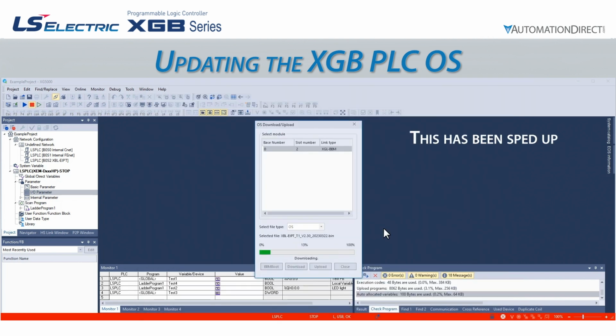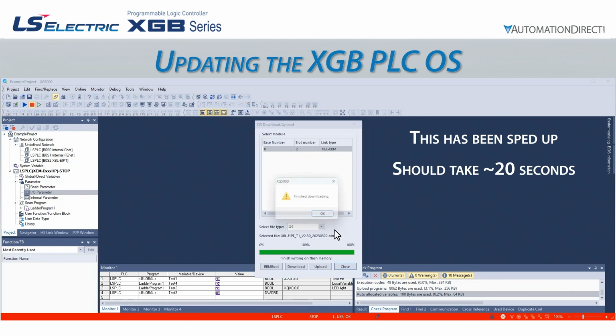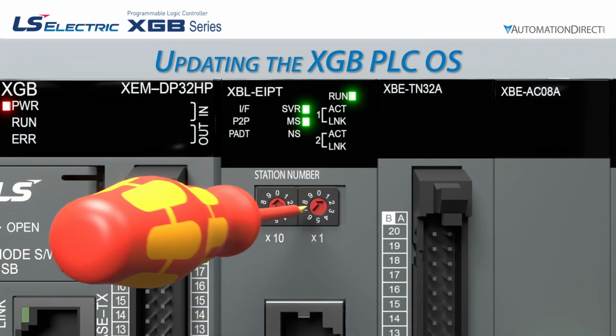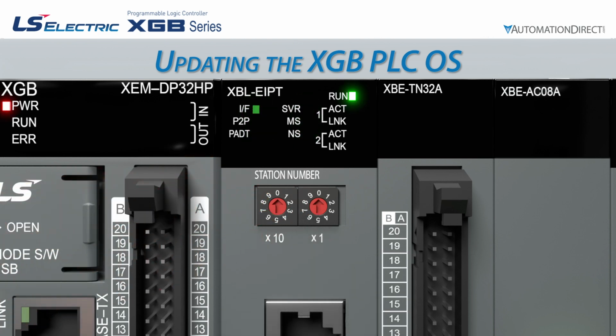The bottom of the OS Download/Upload screen becomes a status bar showing the progress of the OS download. Once the download completes, we will get a confirmation message, and we can put the rotary dial switches back to their original positions and cycle power. Let's verify that the OS has been updated.